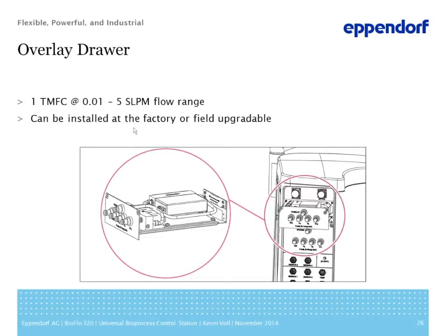And we do the same with our overlay drawer, the headspace gas. We don't offer the same number of configurations. In this case, it's a yes or a no in terms of if it's installed. But if it's not installed up front during the buying process and it's needed down the road, or vice versa, if it's purchased up front and not needed down the road, it can be added or removed in the same time frame, less than 5 minutes. The system will automatically detect whether or not it's there, and it will automatically populate the software as needed.